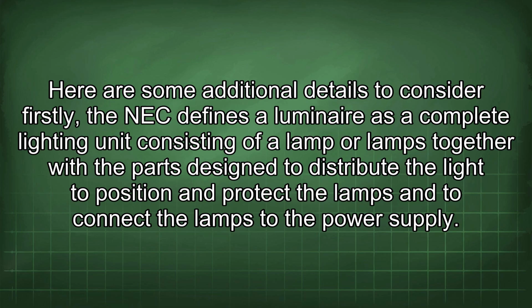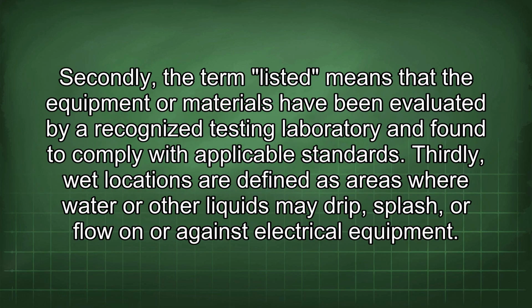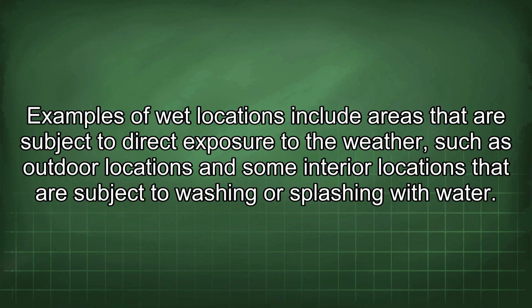Here are some additional details to consider. Firstly, the NEC defines the luminaire as a complete lighting unit consisting of a lamp or lamps together with the parts designed to distribute the light, to position and protect the lamps, and to connect the lamps to the power supply. Secondly, the term listed means that the equipment or materials have been evaluated by a recognized testing laboratory and found to comply with applicable standards. Thirdly, wet locations are defined as areas where water or other liquids may drip, splash, or flow on or against electrical equipment. Examples of wet locations include areas that are subject to direct exposure to the weather, such as outdoor locations, and some interior locations that are subject to washing or splashing with water.